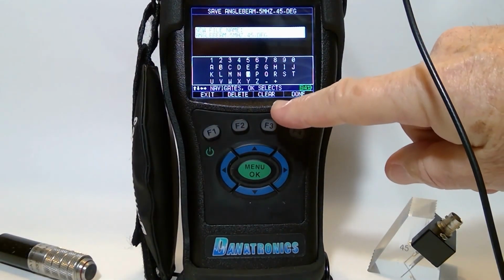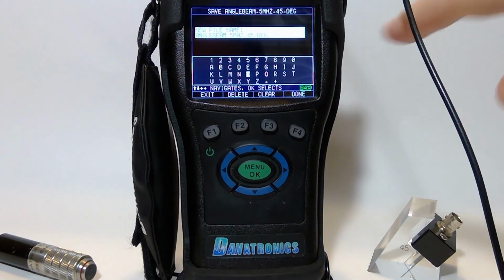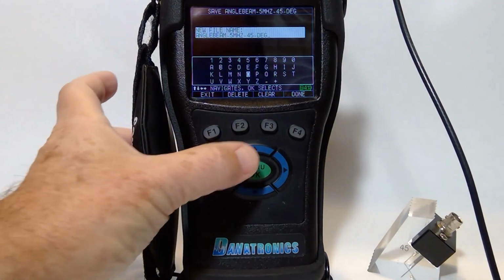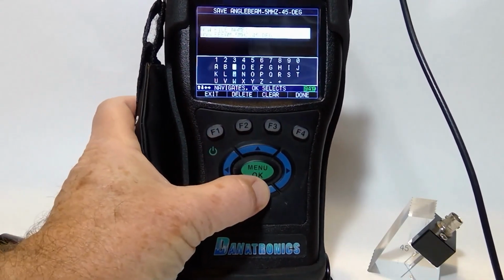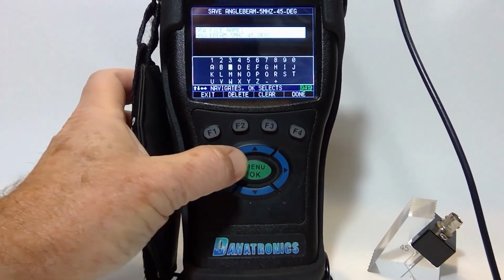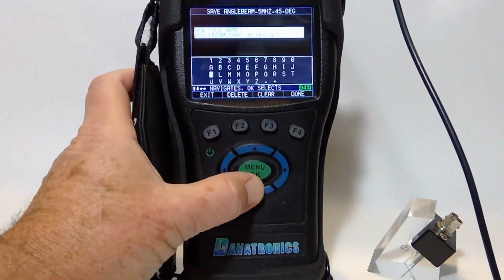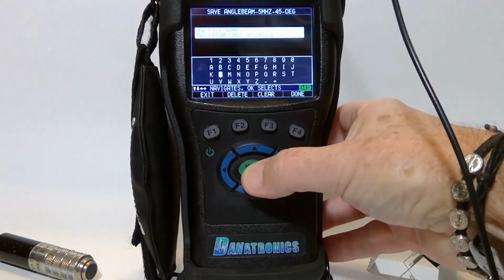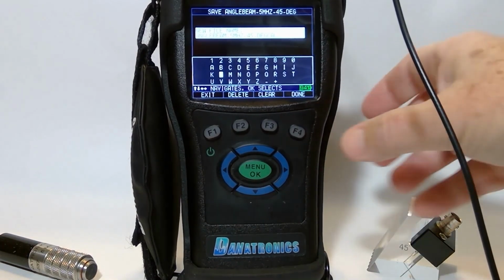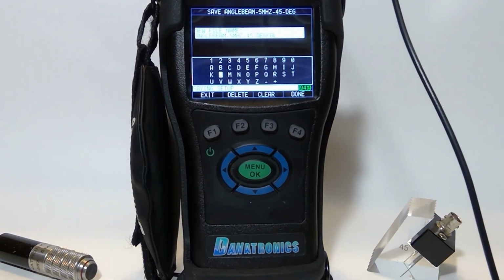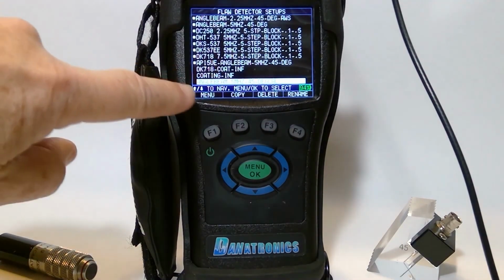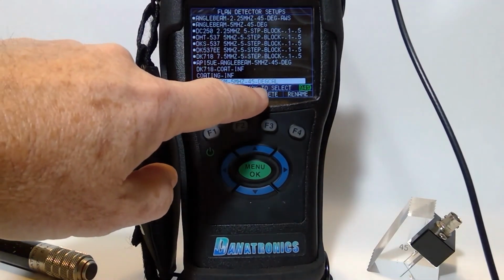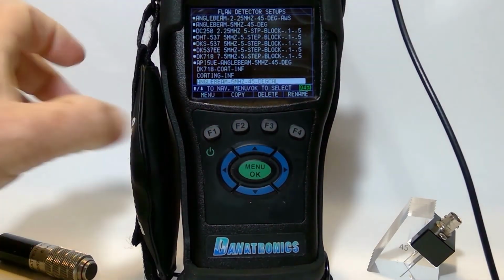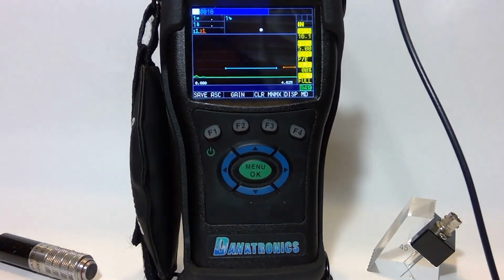I'm going to save it, so I press F2. Now I can either clear that name completely, or I can adjust however I want. I like this description. I'm just going to add cal to it. See? A and L. When I'm finished, I press F4 done. It states that it is saving the setup. And all of the information, now as you see, it is a stored setup, angle beam 5 megahertz, 45 degree cal. So now I can hit OK, and it pulls that back up.